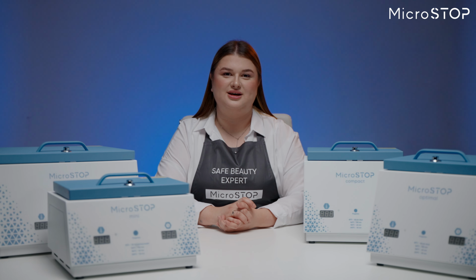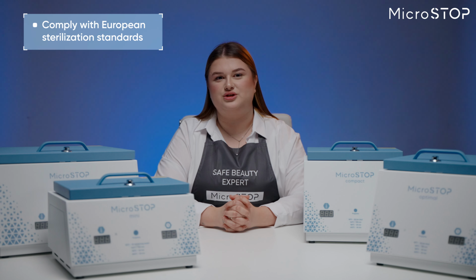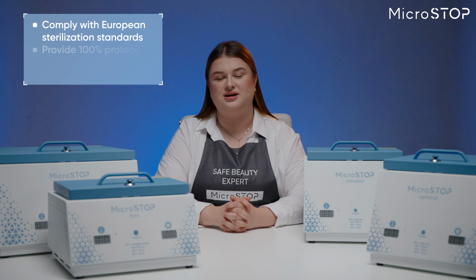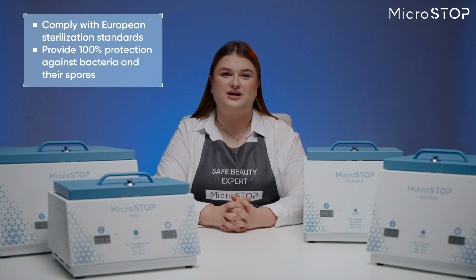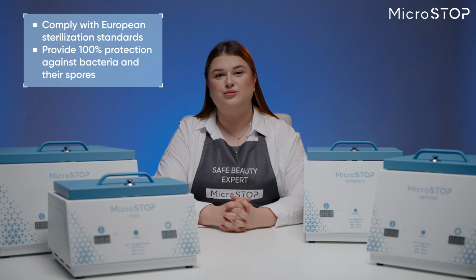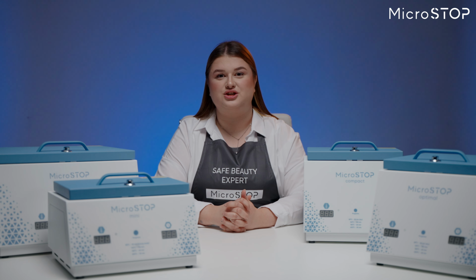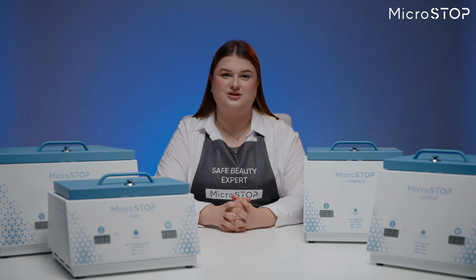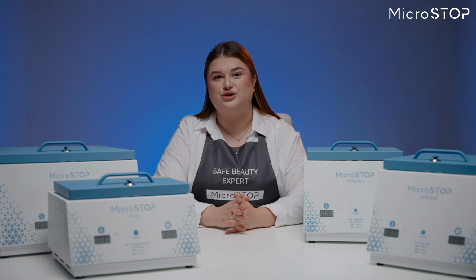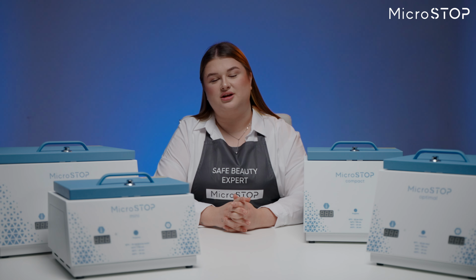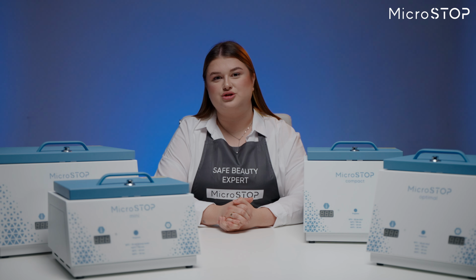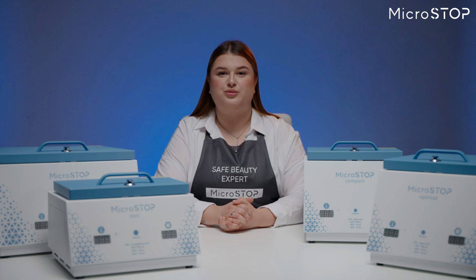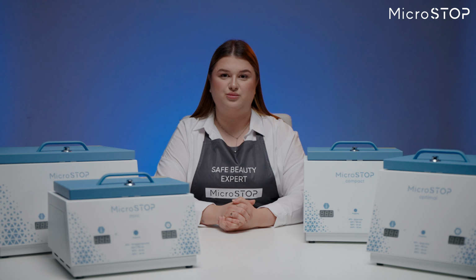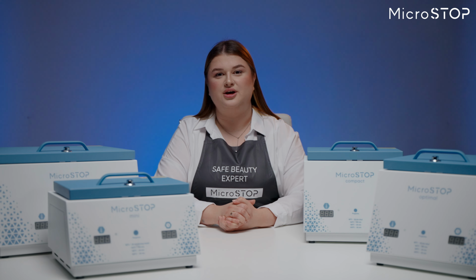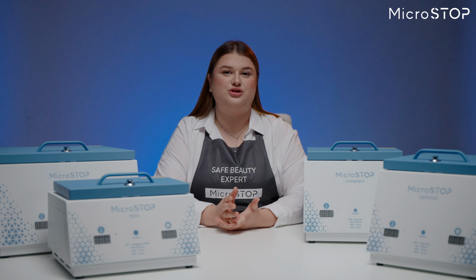All Microstop sterilizers comply with European sterilization standards and provide 100% protection against bacteria and their spores, so you can be sure that your health and life are safe, and therefore your clients and business reputation are safe too. And of course, treating tools in a high-temperature dry heat sterilizer will save your money, as the cost of sterilizing one set of tools in a dry heat sterilizer is almost 11 times less than sterilizing them in a high-pressure steam sterilizer. So why should you pay more for the same result?